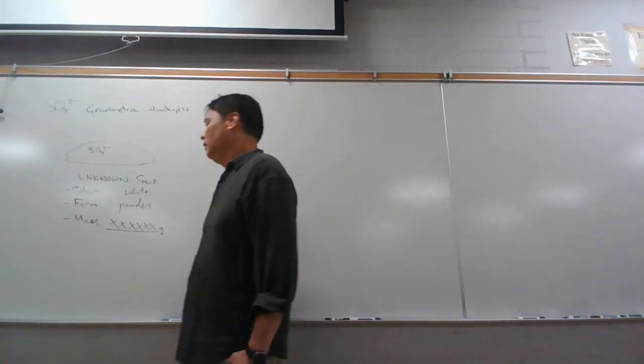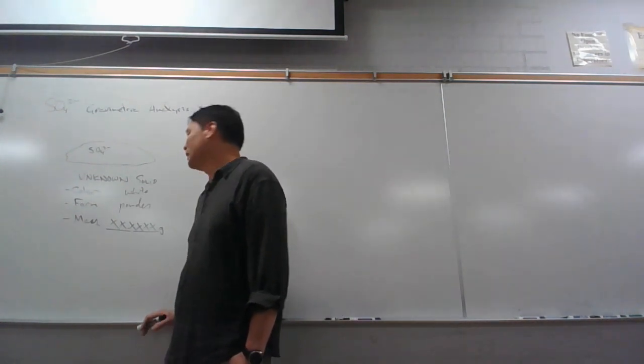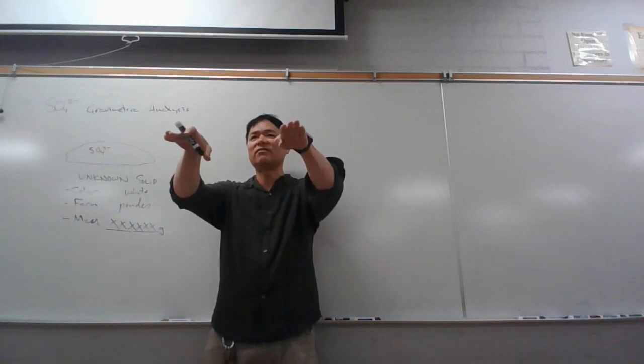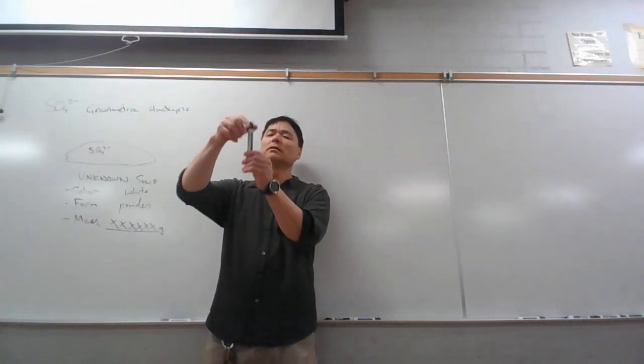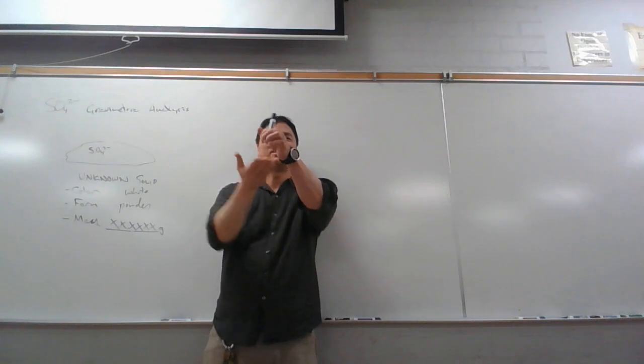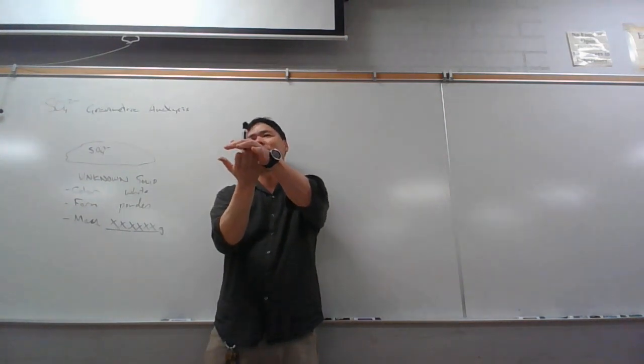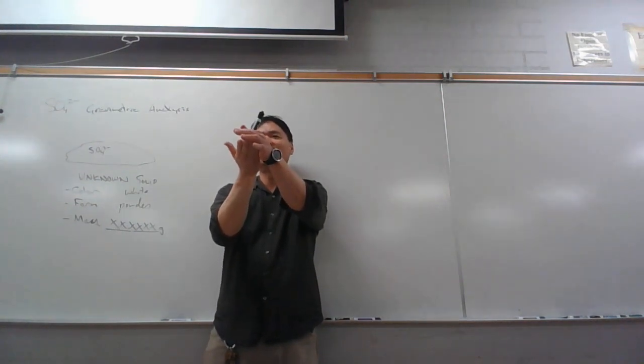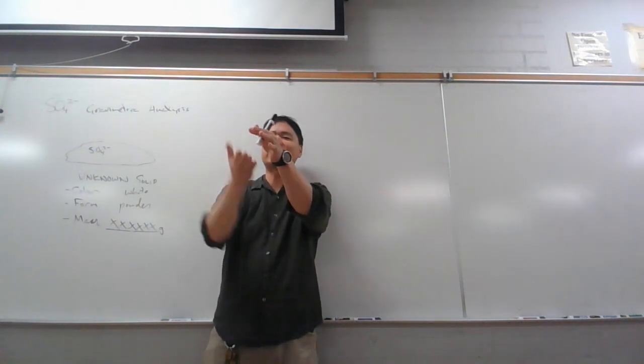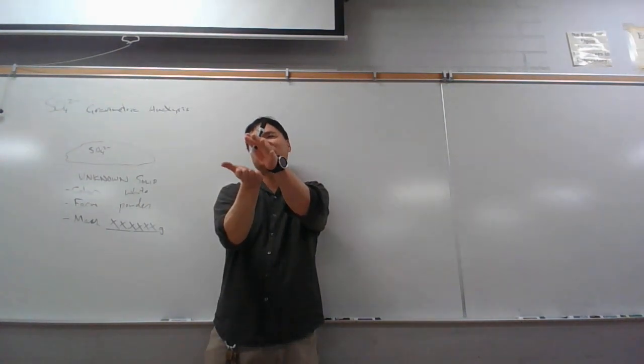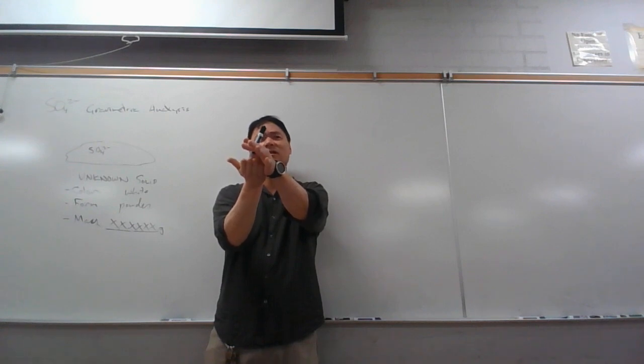The other thing that could cause it to not read correctly is if the balance is not level. The balance has a little plunger that goes in and it records the mass here. If it's tilted a little bit, then the force is not going straight on the, I think it's some kind of spring or some pressure sensitive sensor there.